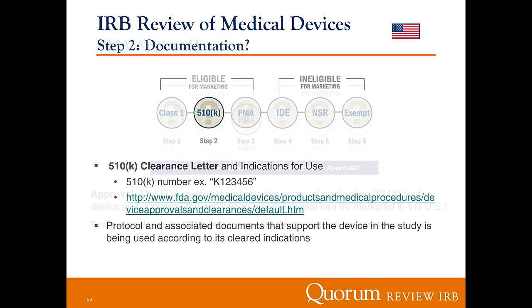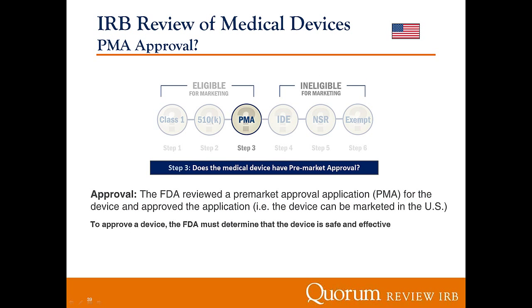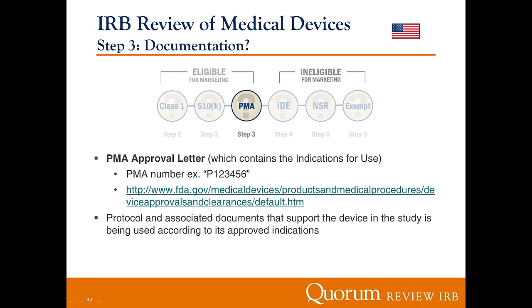Now step three. If it's not a Class 1 and doesn't have a 510K, does it have pre-market approval? Pre-market approval means the FDA has reviewed a pre-market approval application for the device and has approved the application, because through clinical testing and all sorts of data it has determined the device is safe and effective. So what documentation do you need for the IRB to be assured that the device has pre-market approval and is eligible for marketing? Here, as with the 510K letter, you could have the PMA approval letter, which also contains the indications for use.